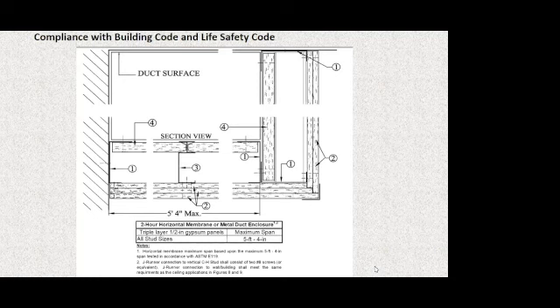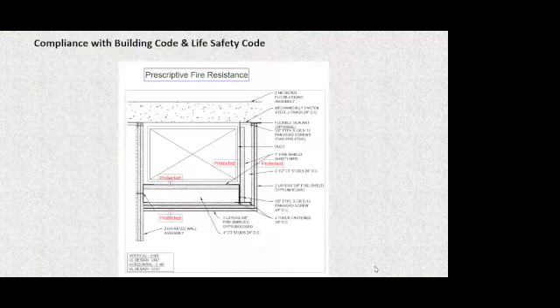And so we can see why a lot of people go to fire-rated ventilation duct, because the fire-rated ventilation duct doesn't have those constraints. Its continuity support is equal, but provides more freedom. So we don't need that 2-hour wall following along the fire-rated duct path, but we have other things that we need to pay attention to that are often overlooked.